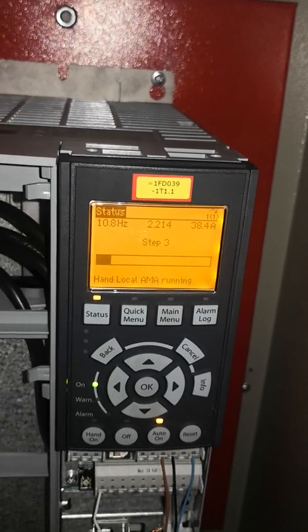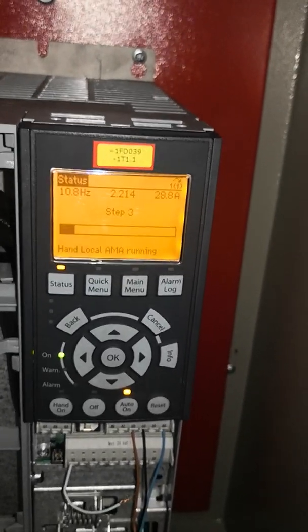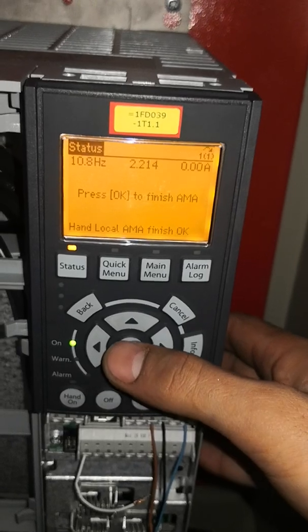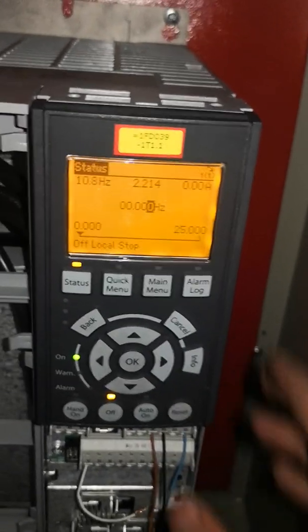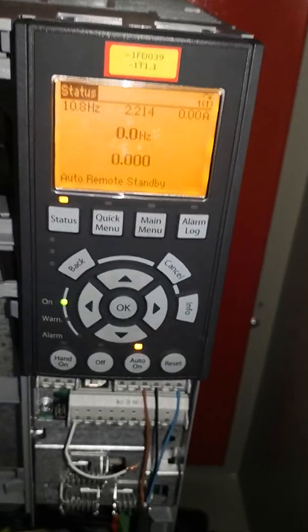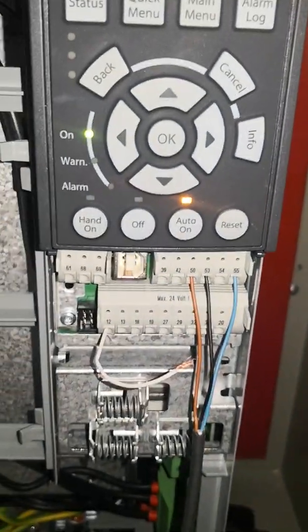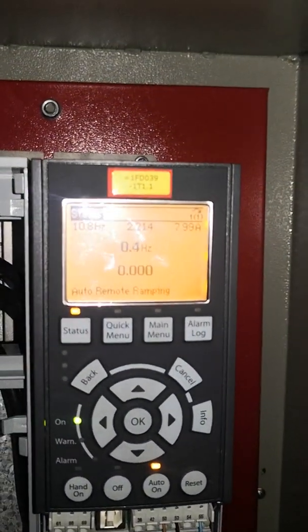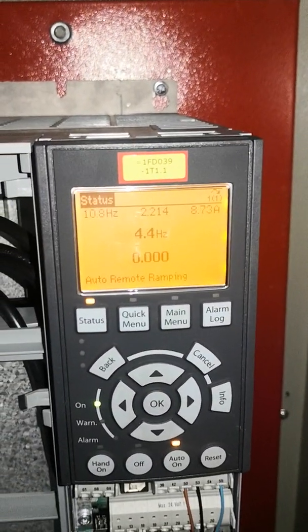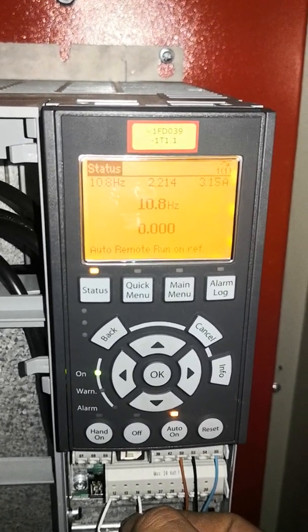After waiting for the AMA process to finish — welcome back. The AMA process is now complete. Press OK, then press Auto. In the Status menu, you can see that connecting terminal 12 to terminal 18 now starts the motor — the Hz value is increasing and the motor is running. Thank you for watching!